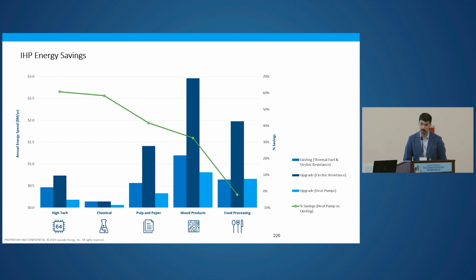So you could see, converting to all electric resistance was a major increase in annual energy spend, whereas converting to all heat pumps resulted in pretty good savings for the most part. High tech and chemical had the highest percent savings, but pulp and paper and wood products, those projects were just larger in magnitude, a little bit lower percent savings.